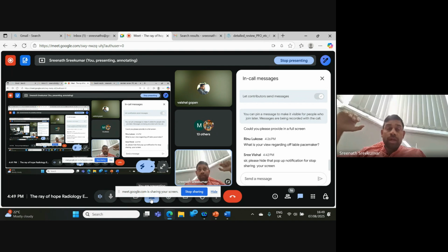But you have to understand the differences in first level mode. If you are scanning a patient with an implant and the implant manufacturer suggests it should be scanned in normal mode, then if you go for first level, the SAR level will be 4 watts. That is not acceptable for the implant, and you can create a risk of burning or other problems for the patient. The projectile risk and the burning risk are both different.